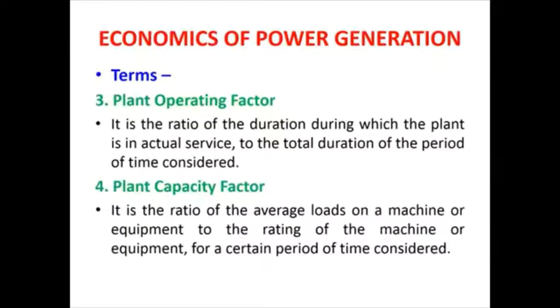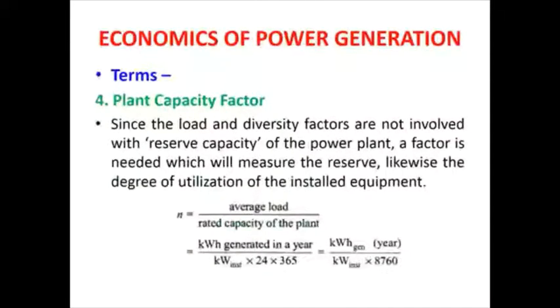Then plant capacity factor. It is the ratio of the average load on a machine or equipment to the rating of the machine or equipment for a certain period of time considered. As compared to plant operating factor, here we consider the capacity of the plant. In this way we calculate the plant capacity factor. Since the load and diversity factors are not involved with the reserve capacity of a power plant, a factor is needed which will measure the reserve, and likewise the degree of utilization of installed equipment. Therefore it is equal to average load divided by rated capacity of the plant.